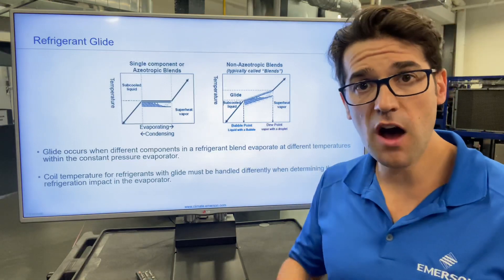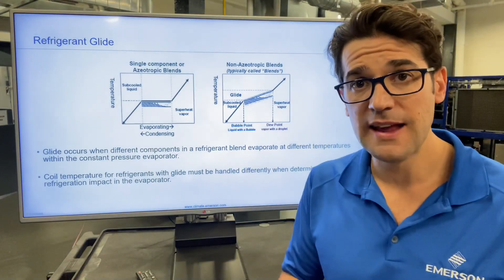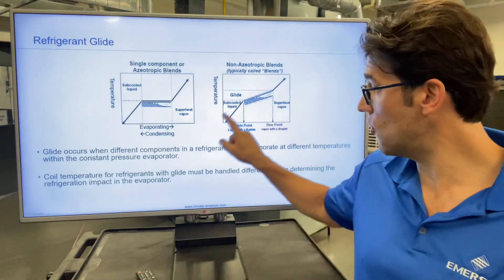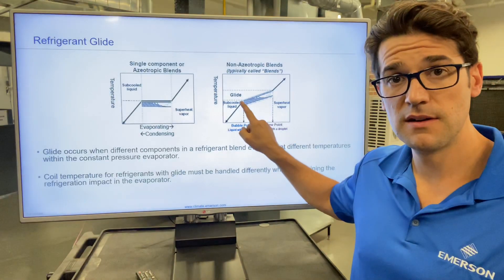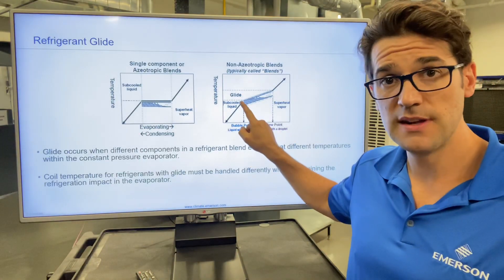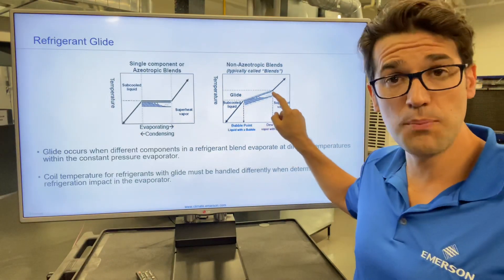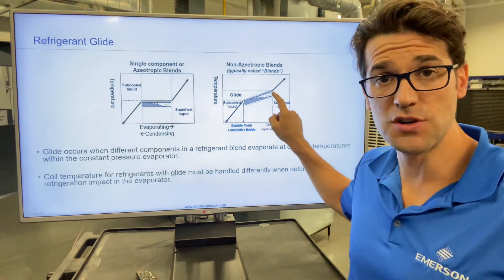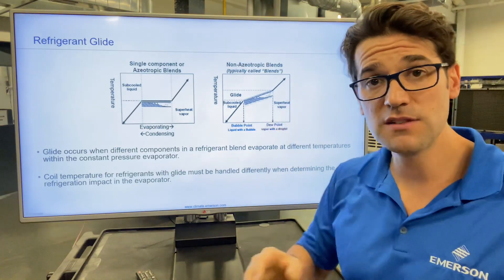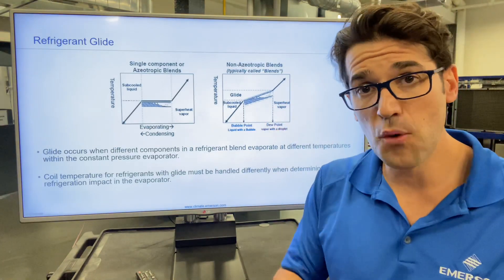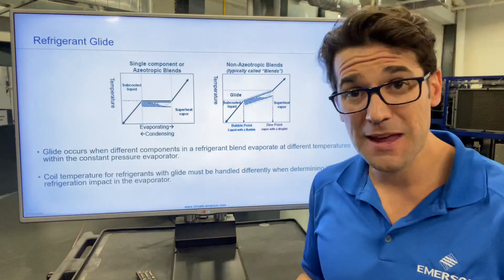they're going to have a high glide. And what glide means is that the bubble point temperature is different than the dew point temperature at a constant pressure, because the refrigerants are boiling off at different temperatures.